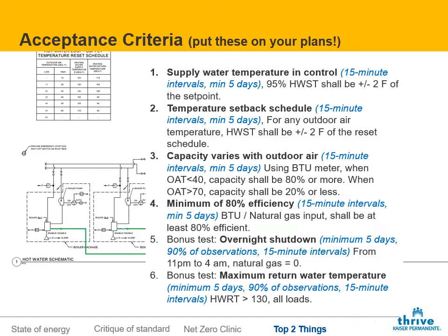First, you want to make sure that the supply water temperature is in control. All the points that you gather on supply water temperature should be plus or minus 2 degrees of the set point that they were intended to be. Second, I would expect that the hot water supply temperature would be working according to a setback schedule. Right? When outside air temperature is below a certain temperature, we should see higher supply water temperatures, and when it's above a certain temperature, then we should see lower supply. That should be extremely predictable, and the data that we gather should fall right in line with our expectations.